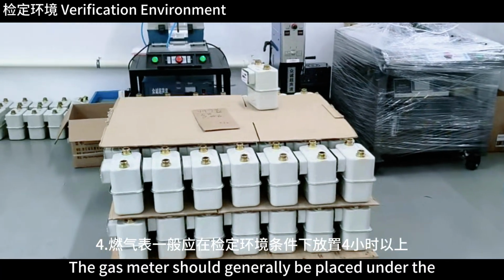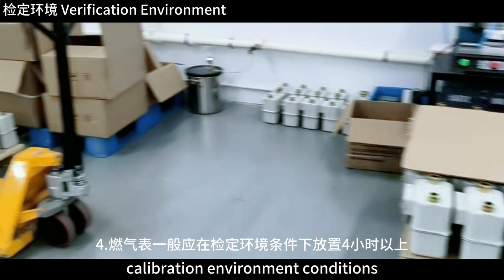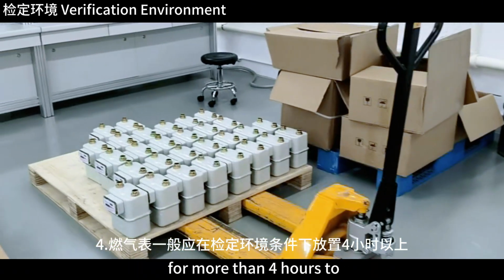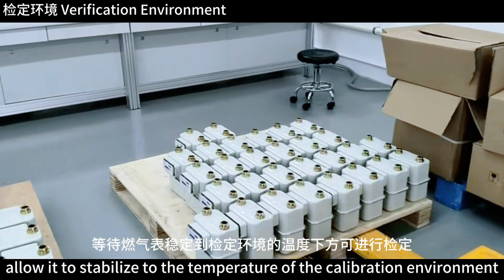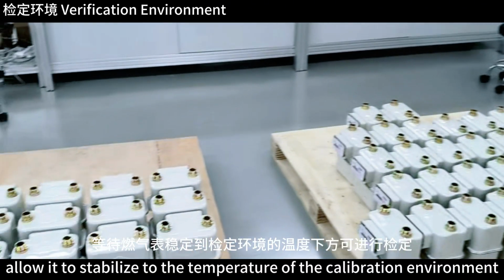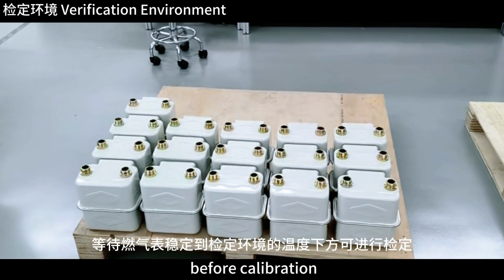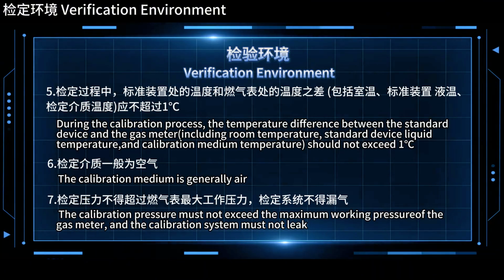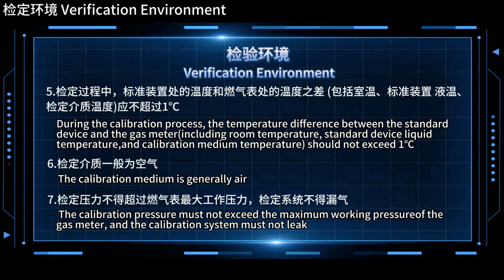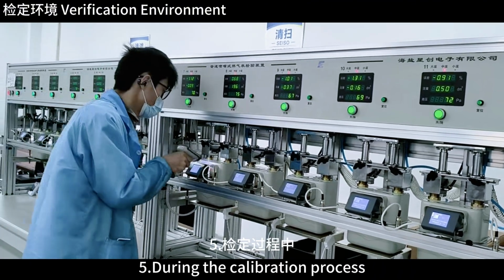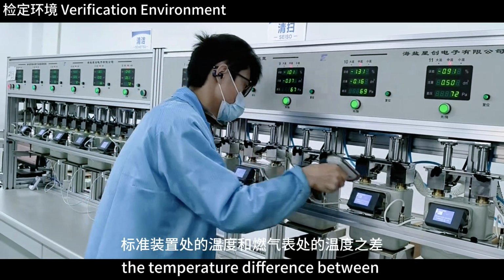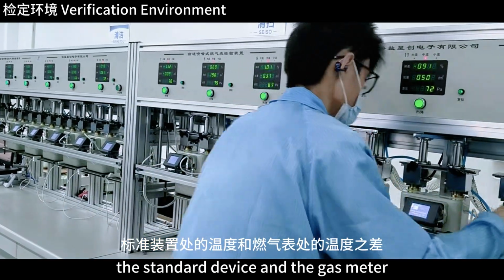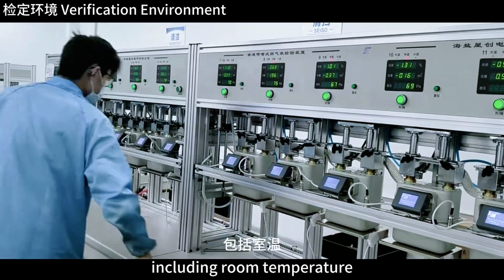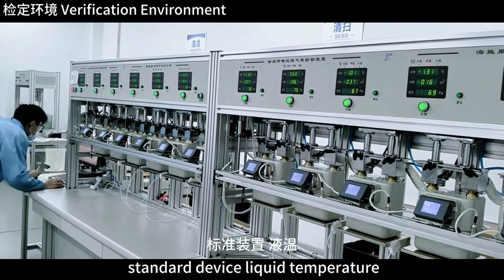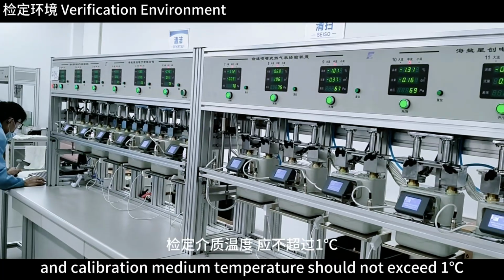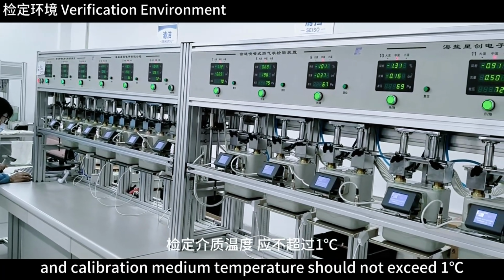4. The gas meter should generally be placed under the calibration environment conditions for more than 4 hours, to allow it to stabilize to the temperature of the calibration environment before calibration. 5. During the calibration process, the temperature difference between the standard device and the gas meter, including room temperature, standard device liquid temperature, and calibration medium temperature, should not exceed 1 degree centigrade.